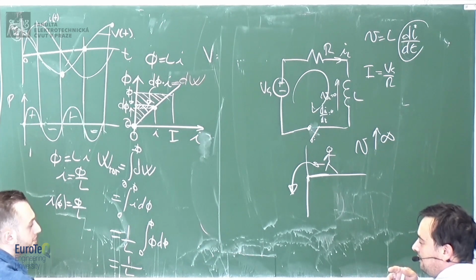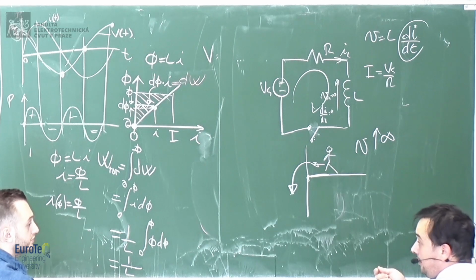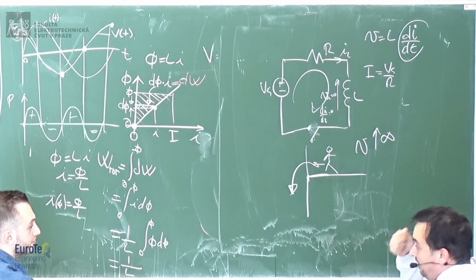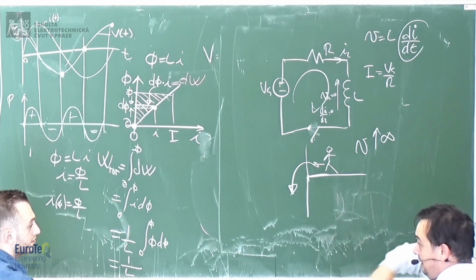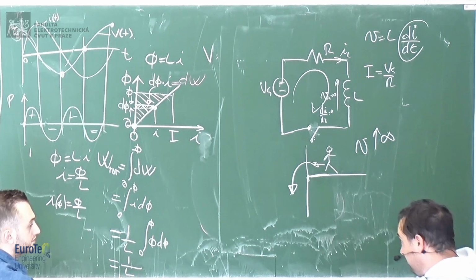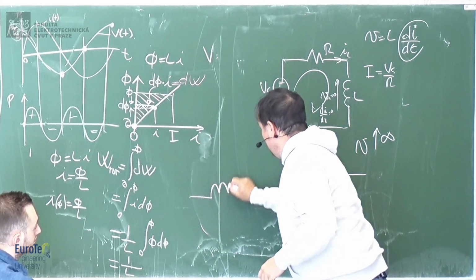in the inductor. This is also why in your class they stressed that when you are using a current transformer, of course, you should have a shunt there. You always have to close it before removing the ammeter, because otherwise you have the current in the secondary which goes through the ammeter, which is a short.